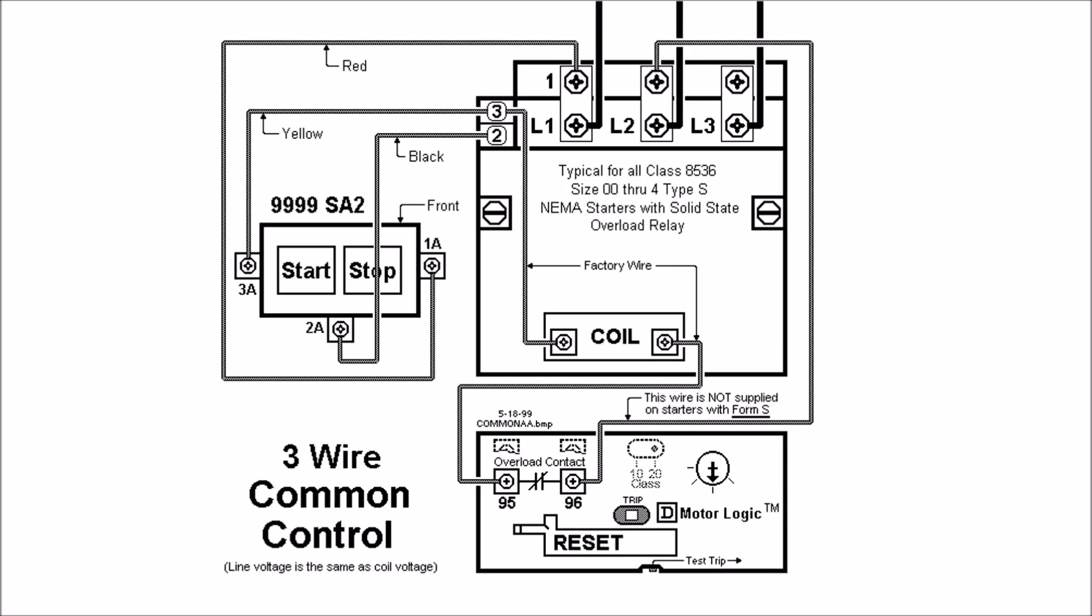For common control the wiring is just a little bit different. You'll actually get a type S starter if it does not have that form S on it where it's set up for common to control there will be a red wire from terminal L2.